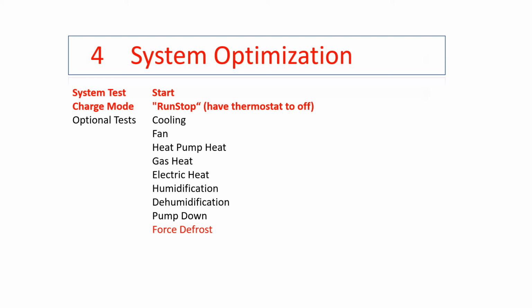Our second one is charge mode. When we're done doing our system test and we want to check subcooling, or if you're on a service call and you want to look at the subcooling, that's done under optimization for charge mode. Please check it there and not under the cooling optional test. But you do have the capability here to run the gas heat, to check your delta T, to run the electric heat, which is especially nice on a heat pump.